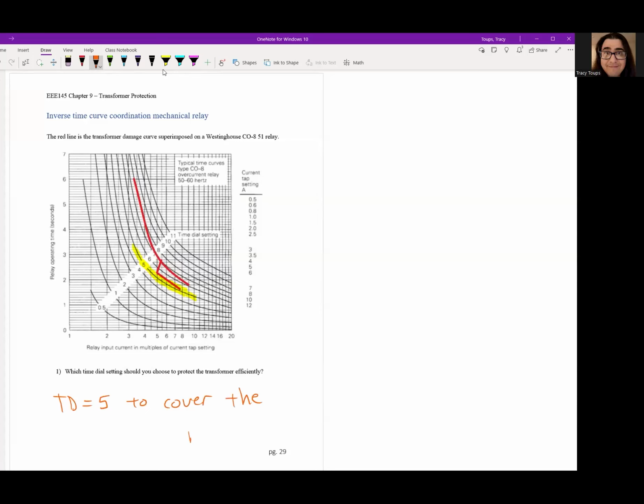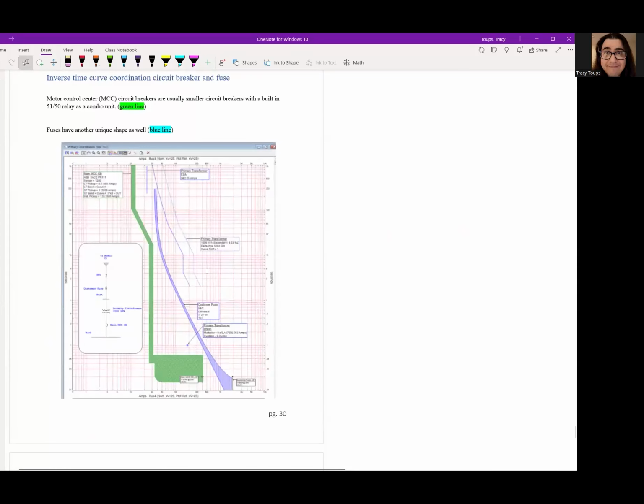both the mechanical and the thermal damage curves. Okay. And you're pretty much set for the time dial. You're coordinated. There will be other things you need to coordinate with, but typically the transformer overcurrent relay is the one right next to the transformer damage curve. Right. There will be other things you need to coordinate, like circuit downstream devices.